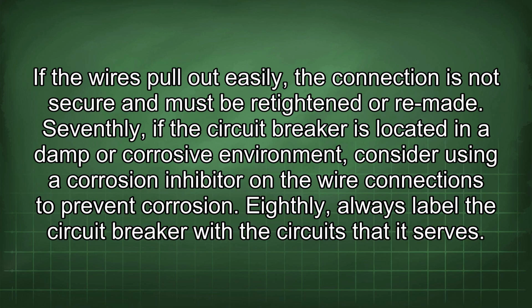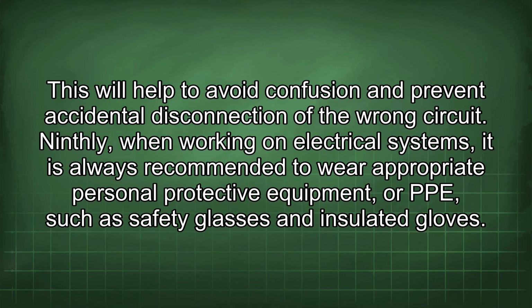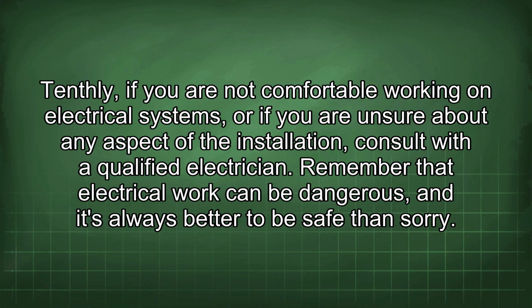Seventhly, if the circuit breaker is located in a damp or corrosive environment, consider using a corrosion inhibitor in the wire connections to prevent corrosion. Eighthly, always label the circuit breaker with the circuits that it serves. This will help to avoid confusion and prevent accidental disconnection of the wrong circuit. Ninthly, when working on electrical systems, it is always recommended to wear appropriate personal protective equipment, or PPE, such as safety glasses and insulated gloves. Tenthly, if you are not comfortable working on electrical systems, or if you are unsure about any aspect of the installation, consult with a qualified electrician. Remember that electrical work can be dangerous, and it's always better to be safe than sorry.